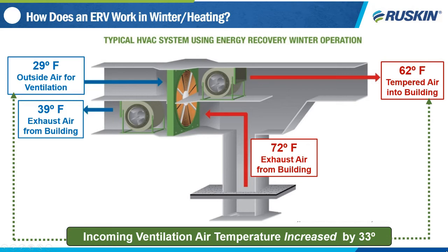Here you're looking again, I picked Kansas City. Kansas City design conditions, 29 degrees outside, 72 degrees in your building. Traditionally, you would be exhausting this 72 degree air outside, and your system would be responsible for heating up this 29 degree air. What you see here is that nice warm 72 degree air goes over the wheel.